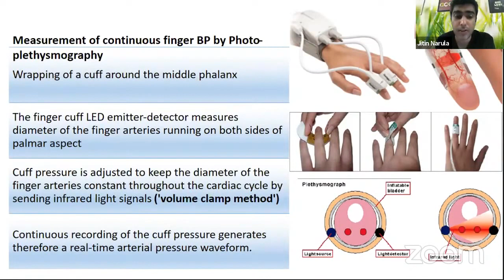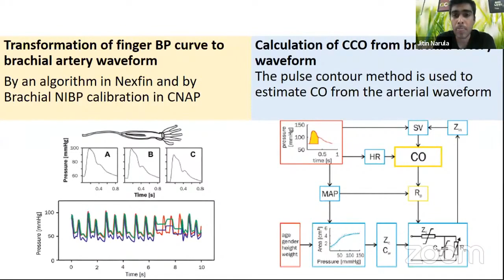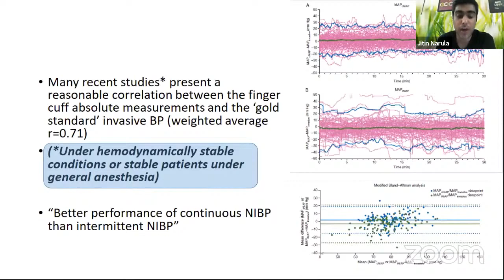Continuous recording of cuff pressure generates, therefore, a real-time arterial pressure waveform. Transformation of the finger BP curve to the brachial artery pressure waveform is then done by an algorithm in the Nexfin and by a brachial NIBP calibration in the CNAP monitor. Calculation of cardiac output from the brachial artery waveform is then performed using the standard pulse contour method. Many recent studies present a reasonable correlation between the finger cuff absolute measurement and the gold standard invasive blood pressure. However, most of these studies have been performed under hemodynamically stable conditions or stable patients under general anesthesia. However, it has been shown that there is better performance of continuous NIBP than intermittent NIBP.